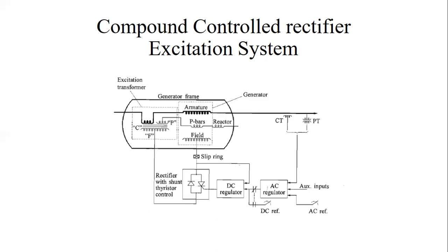The excitation transformer consists of three single phase units with three windings: current, potential, that is voltage, primary windings, and the secondary output winding. Under the fault condition, the fault current flowing through the excitation transformer current winding provides the field forcing capability when the generator's voltage is depressed.